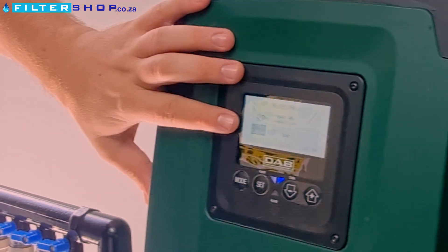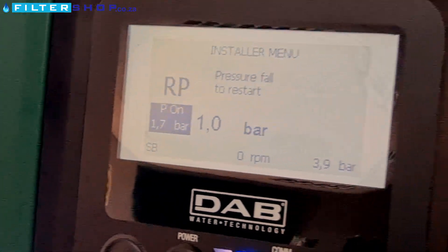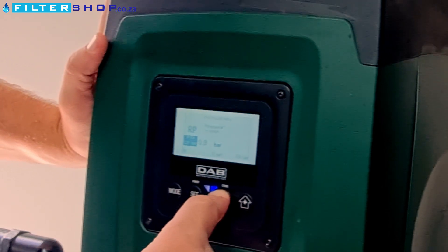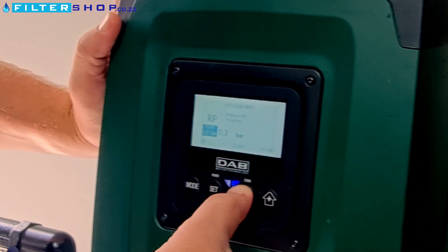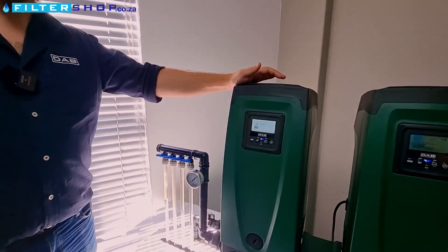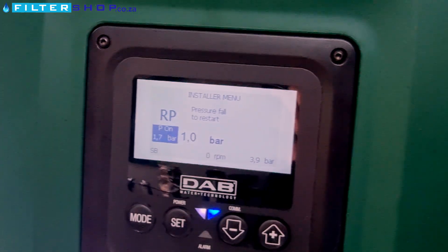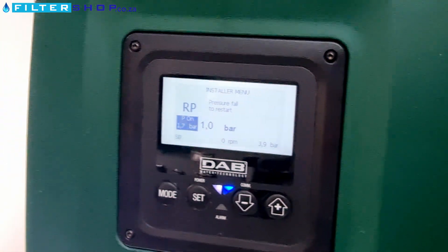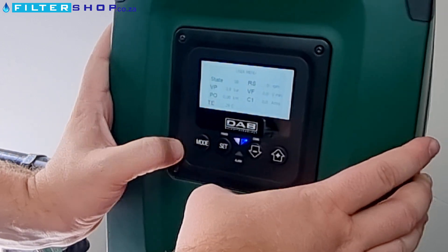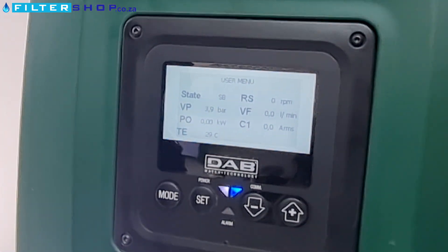It is pressure fall to restart. And how low can you set it — is it a percentage or is it a bar value? It's a bar value, so you can go all the way down to 0.1. Maximum one bar drop — yes, okay. So it can't drop more than one bar before it restarts. So this is giving us real world data where we're running.